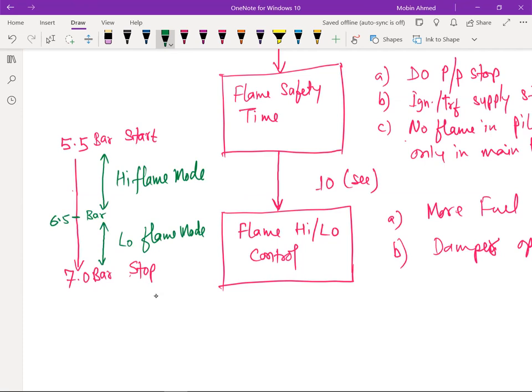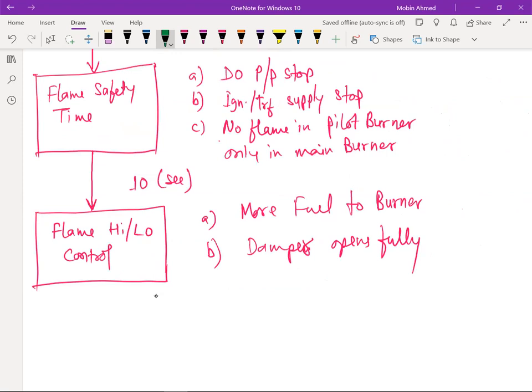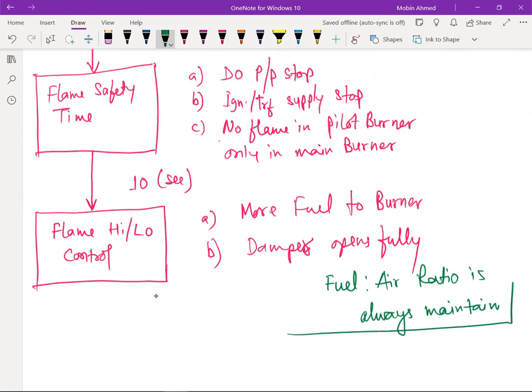This is basically the fuel and the damper. If it is a solenoid type, the solenoid is going to operate, and if it is a servo motor type, the servo motor is going to operate. So the fuel and air ratio is always maintained. Remember this. If your fuel is going, your damper is also going to open accordingly. So it is a high flame mode or low flame mode control.